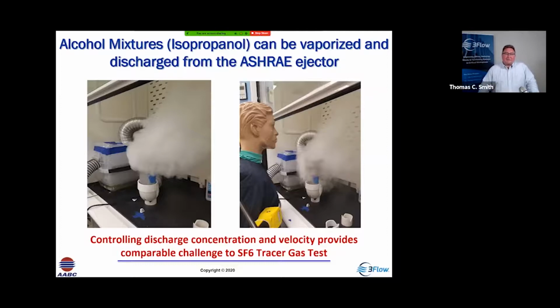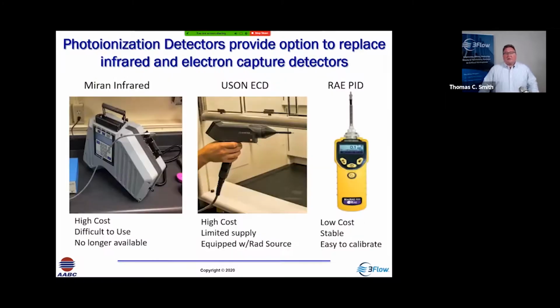And the nice thing about isopropyl alcohol is it's also non-hazardous. It's a flammable material, but it's clean, it's green, it's less than 50% of CO2 in greenhouse gas emission, making it 48,000 times less potent than SF6. And as opposed to $15 per test, it's about $1.25 to use isopropyl alcohol. So we're investigating this for the next ASHRAE 110 standard, and then we'd use a photoionization detector to detect the concentrations escaping out of the hood. So this looks like a really potential challenge for replacing SF6.